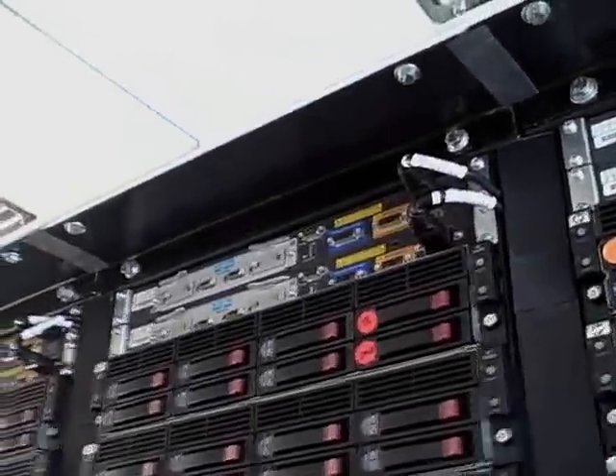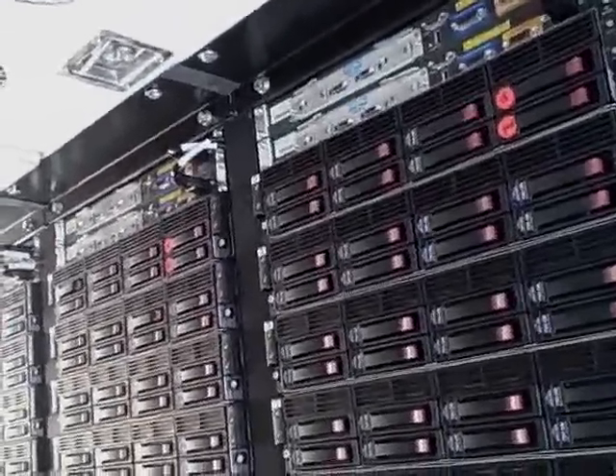It's because we have complete control of the environment that we don't have to cool the data center down to 65 or 75 degrees. All of the major components are overhead — as you see above us, we have the blowers bringing the air through, and the heat exchangers are on top of the racks themselves. Cold air comes down from the blowers, goes through the IT equipment, up into the hot aisle, and then circulates through the heat exchanger in a continuous loop. The pod monitors the ambient temperature and turns the blowers up and down accordingly, then reports that to the customer's building management system.